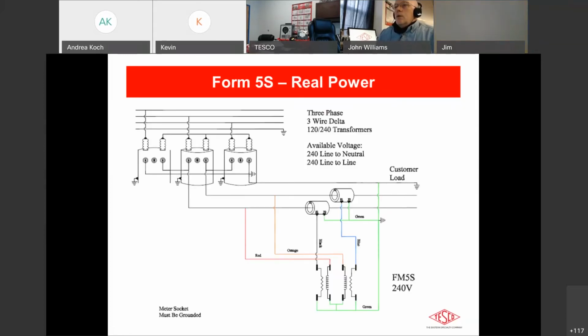The next one is the Jack of all trades 5S meter. Tom referred to that earlier in the Blondel discussion. This is kind of like I said, the Jack of all trades. I picked a 3-phase delta application here for the real installation type. Here you see we have the 3 phases wired to the two potential coils, and then the 2 CTs going out to the 2 current elements on the 5S. Of course, as most of us know, the 5S is probably the one that can be used in the most different situations. You can use this on a straight up single phase.